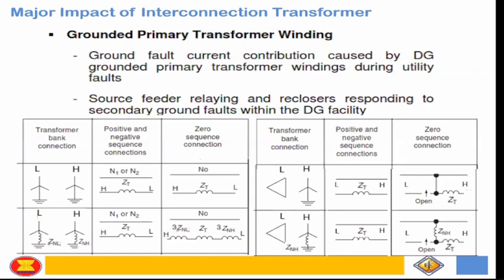So actually, my experience, no, mayroong isang distributed generation, then although during tripping, no, of that recloser, no, dedicated recloser at their end, kasi mayroon silang sa connection point, the distribution utility requires them to have that recloser. Okay, then they have Y grounded primary, delta secondary, no, and then the distributed generation has synchronous generator at that time. But nang nagka-fault, no, single line to ground fault, yung distribution line which the DG is being connected, nag-trip sila, no, nag-participate sila. So palaging nag-minis-operate. Okay?